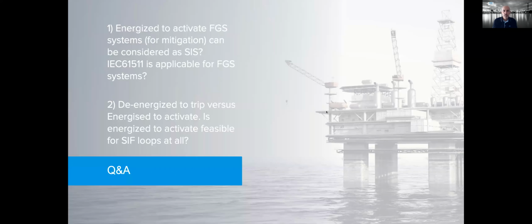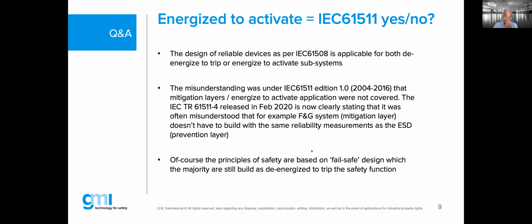Okay, Tino, thank you. So the next question is: can energized to activate fire and gas systems for mitigation be considered as SIS? IEC 61511 is applicable for fire and gas systems, and also for de-energized to trip versus energized to activate. Is energized to activate feasible for an SIF loop at all? Well, we can be very short on that answer because we have been answering it in the webinar, and it was also mixed in on the previous questions.